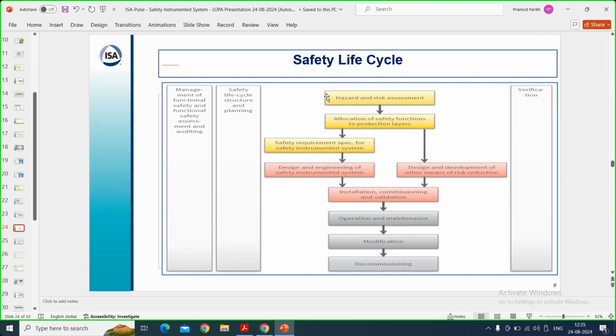Yes, sir. Suppose you have installed a SIL 3 level system when SIL 3 was required, but you are not doing any proof testing, like I mentioned. If you are not periodically testing, your SIL 3 can get deteriorated to SIL 2, SIL 2 can get deteriorated to SIL 1, it can give you 0 level also. A plant with SIL 3 rating but not tested for 5 years will give you 0 SIL performance.